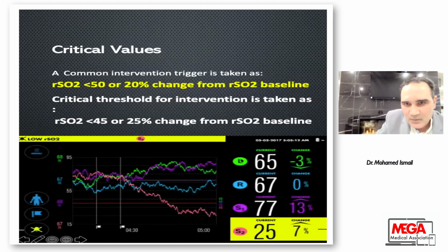We see here both sides are monitored. The left side is 65, which is great, it's above 50, and the right side is 67, which is also great. And the change on the right side is 0% from the baseline. The change on the left side is minus 3%, which is less than 10%, so it's acceptable, and we don't have to do anything about it. So it gives us both right and left side readings at the same time.